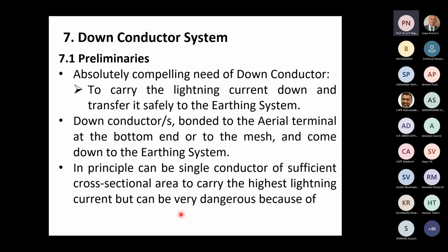It's a no. Let me repeat. A single down conductor is a no. Therefore, absolute minimum is 2, but even that is not at all advisable. At least 4 conductors would be better. 4 conductors, for example, at the 4 corners of a building. Even though the rod may be 1 at the top, 4 down conductors at the 4 corners will be very, very desirable.